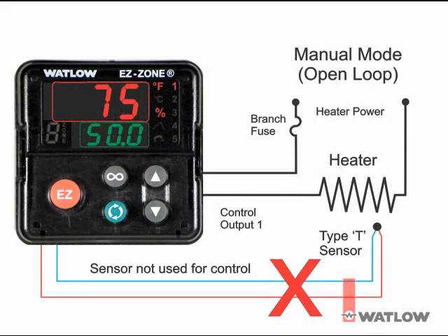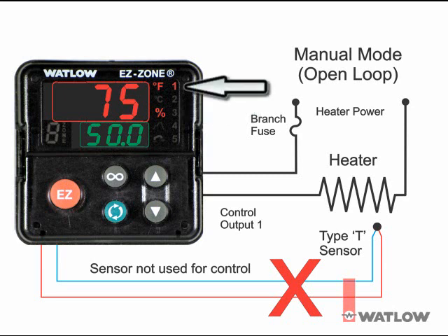In Manual mode, the controller does not use the sensor input to control the load, but operates in open loop. The controller still updates the readings from the sensor if connected. The user specifies the amount of power to supply the load. The percent indicator shows the manual setpoint is in power. The output indicator flashes at a rate proportional to the selected output.